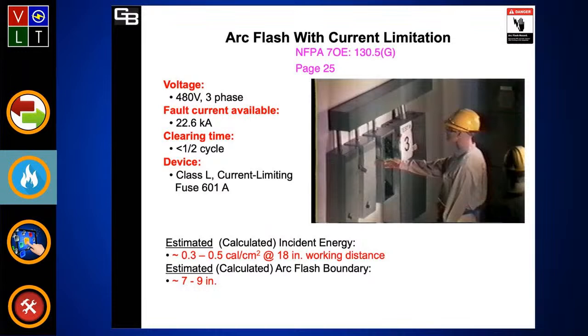This illustration shows an arc flash with current limitation. Notice it's about 22.6 kA, and I'm showing a clearing time of a half cycle. The protective device upstream will clear in about a half cycle. I'd like you to see, by using a current limiting or energy reducing type device, just how the available short circuit current due to electrical arc is reduced.